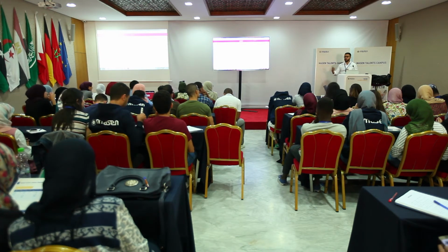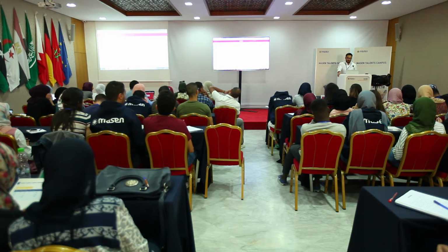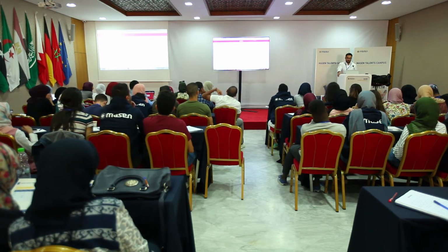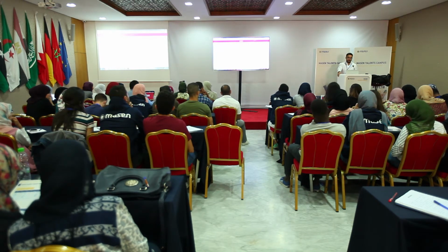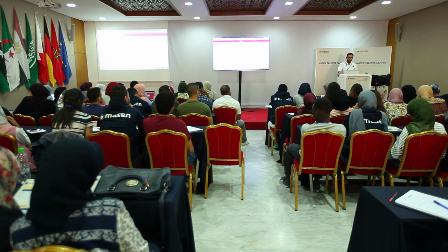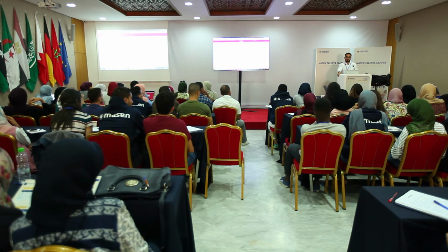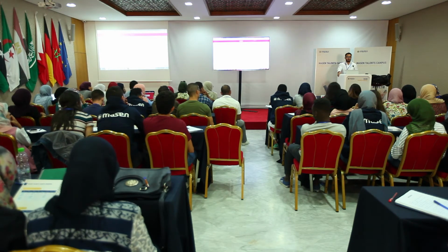And why do most CSP plants in the world use sensible heat storage, even though latent heat storage can store more than sensible heat storage systems? Well, it's not true that one can store more than the other, because it depends on how you size them. But what is true is that latent systems are more dense, meaning that per cubic meter, they can store more than a cubic meter of sensible heat. So from that perspective, it is true.